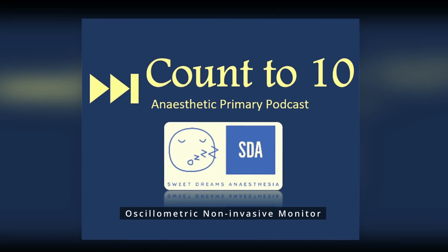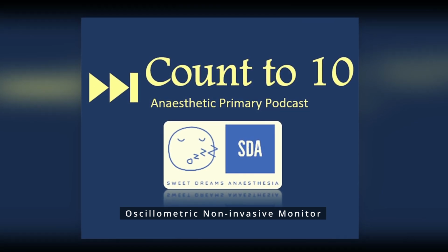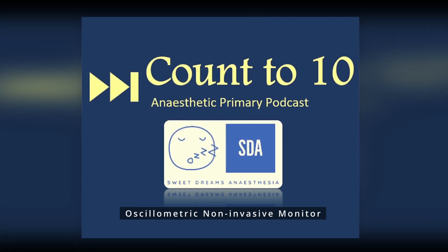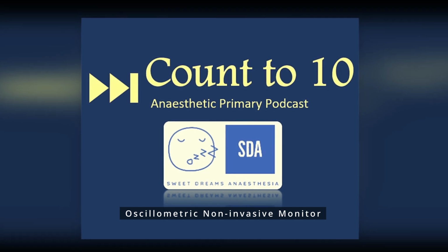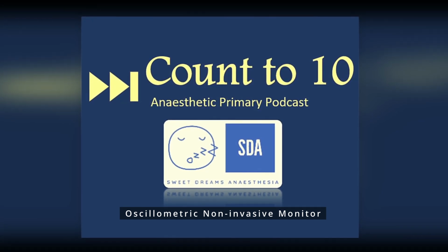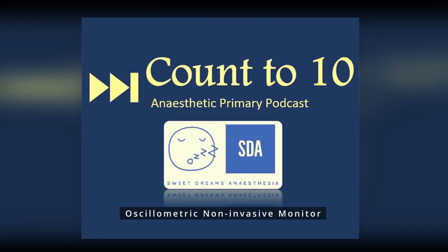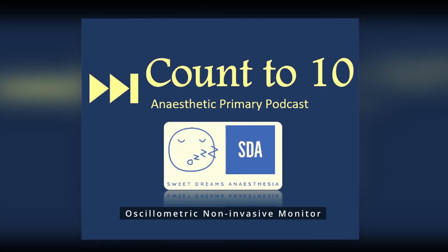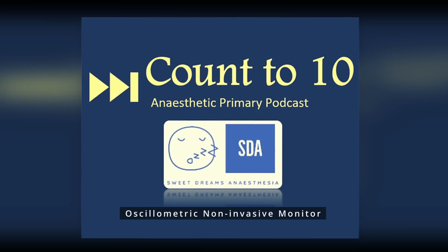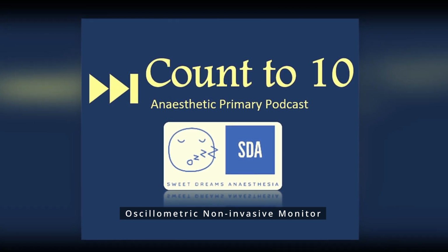The main disadvantage of this technique is that the diastolic blood pressure can be inaccurate. If you have movement to the patient, this will alter the oscillations being recorded by the transducer and lead to inaccurate measurement, or, as you classically see intraoperatively, leads to the blood pressure recycling again and then waiting an extra minute or 30 seconds to get a new reading.